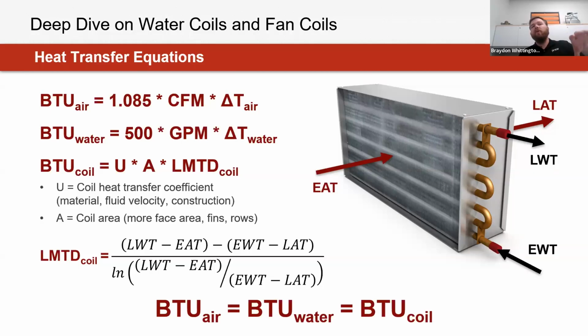It can be a pretty complex formula, I would say, as an initial viewpoint. But at the manufacturing level, typically for the different software that you might use, whether it be Trane Trace or an Engineering Toolkit, all of that manufacturer performance is built into those software tools, just to be able to evaluate how much actual capacity has been measured from that manufacturer for the performance that that coil is going to provide.